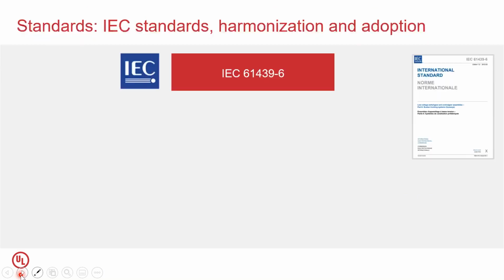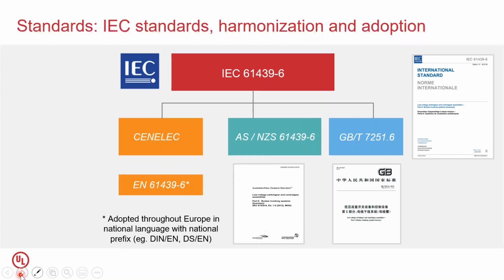Now at the high end, the IEC published the 61439-6 with the inputs of all the national committee members. And then we had this particular standard published. Subsequently, after the 61439-6 was published, we had the group standard called the CENELEC standard. It is called EN 61439-6. Remember, the difference between the IEC 61439-6 and the rest of these standards, what you see here, is the respective national deviations. For example, EN 61439-6 may have certain national deviations that could be applicable within Europe.